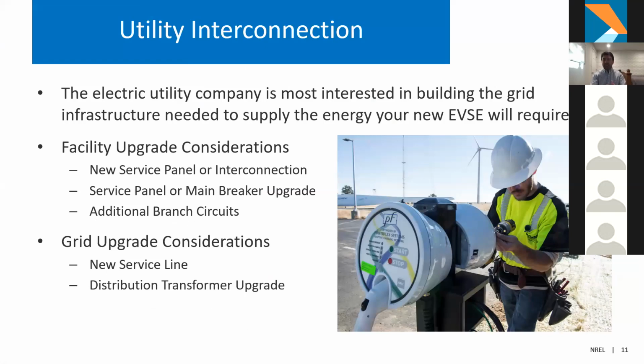So as I mentioned, the utility company is most interested in building the grid infrastructure needed to supply the energy your new EVSE will require. That's essentially saying that for all of the equipment on the grid, it needs to make sure that it's sufficient to supply the electricity at the highest load scenario. So if you happen to install 10 EVSE, the equipment needs to be able to supply electricity in the event all 10 were turned on. And so does your facility. So if you're installing 10 new EVSE, you'll probably also need to install 10 new breakers and make sure that you have the sufficient panel capacity to support that new equipment.